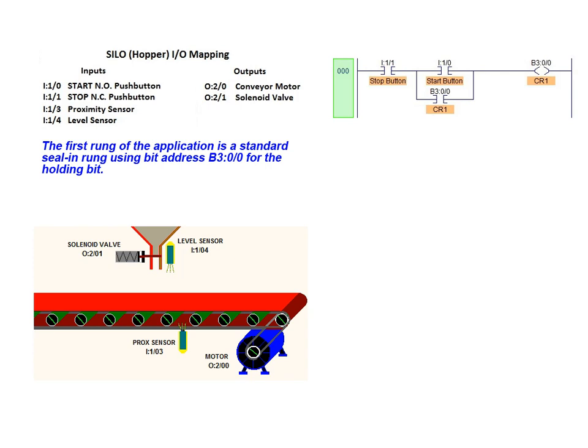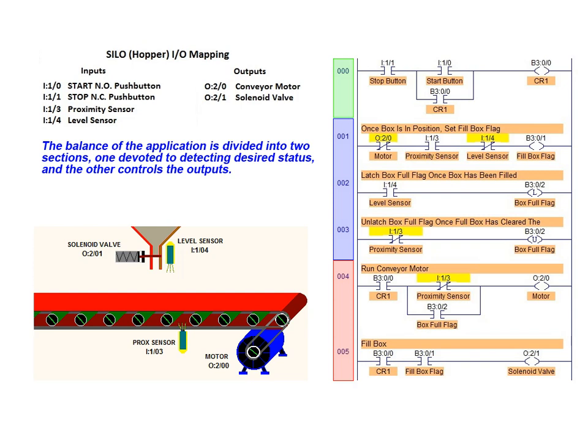The first rung of the program for this application is a standard seal-in rung, which uses bit address B3:0/0 for the holding bit. The balance of the application is divided into two sections: one section is devoted to detecting desired status in the program, and the other section is used to control the state of the outputs in the application.